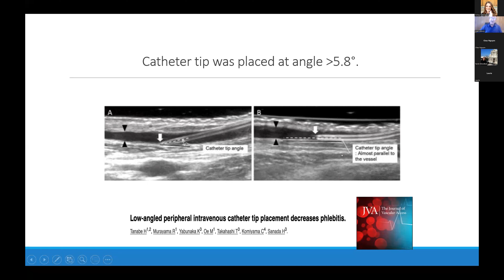What we need is a catheter that's either floating in the center of the vein, which has to do with diameter and a big enough vein. If we don't have a big enough vein for that catheter to float in the middle, it needs to be parallel. It all has to do with the length of the catheter you're using and the depth of the vessel you're sticking. This is one of the most interesting studies that I've read, and it really speaks to why failures occur, honestly.